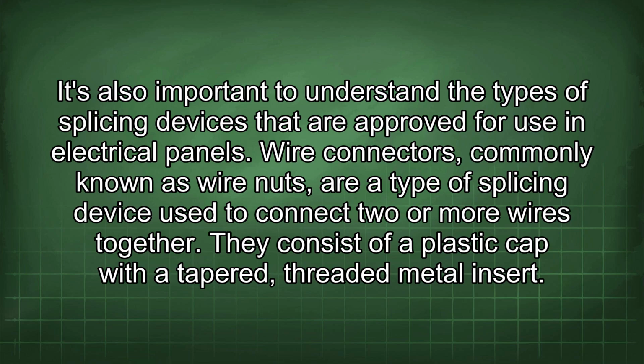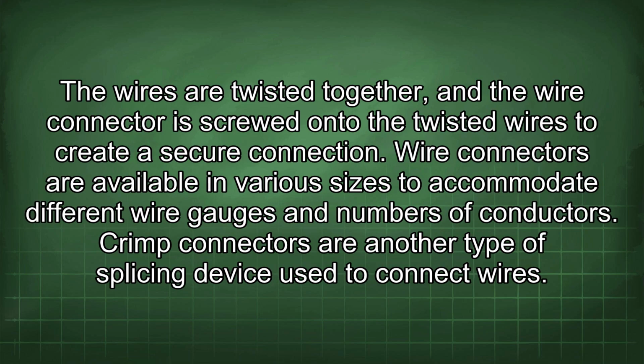It's also important to understand the types of splicing devices that are approved for use in electrical panels. Wire connectors, commonly known as wire nuts, are a type of splicing device used to connect two or more wires together. They consist of a plastic cap with a tapered, threaded metal insert. The wires are twisted together and the wire connector is screwed onto the twisted wires to create a secure connection. Wire connectors are available in various sizes to accommodate different wire gauges and numbers of conductors.